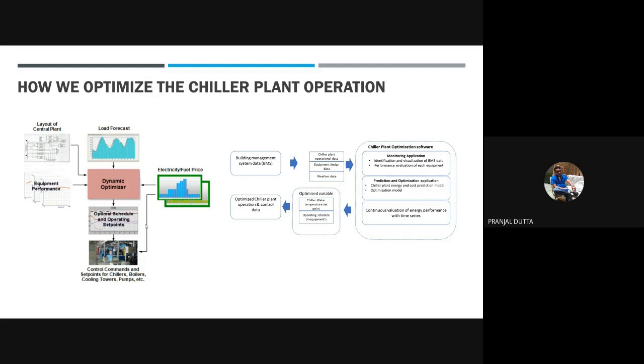Let's say there are two types of chillers. One is, for example, York, this is VSD chillers. One is non-VSD chillers. Then it will always prioritize running the VSD chiller because VSD chillers can run on part load. If a non-VSD chiller runs on part load, its consumption will go high. So it can make its own decision on which chiller needs to be run and what temperature needs to be maintained.